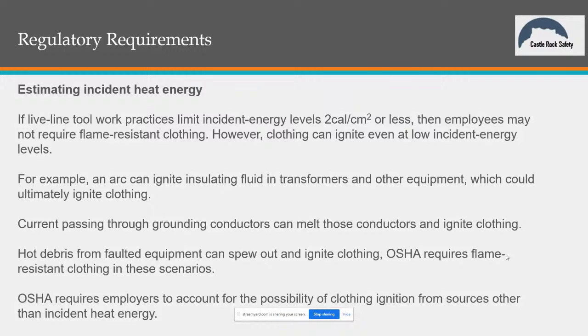Gotcha. And of course it talks about how even though I'm outside the boundary, I could still get burnt from fluid from transformers, grounding conductors melting, hot debris from faulted equipment. And then OSHA requires flame resistant clothing in these scenarios. So it's kind of weird the way they write this stuff, guys. They're saying, yeah, if you're working up here, you got to have the arc flash clothing on. If you're outside that, you could still catch on fire, so you need flame resistant clothing on. And it's just nonsense to try to manage 2 different types of clothing, of course. So you're going to wear your arc flash clothing.